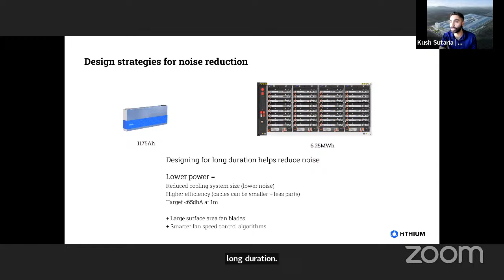We're trying to use larger flat fan blades, as well as smarter fan speed control algorithms which modulate the speed of the fan so it's not running at full power all the time, giving more granular control of fan speed. For this, we're targeting around 65 dBA at 1 meter. So despite having more energy because you're running it slower, that will reduce the noise. This may be something you see more of in the industry, batteries being designed specifically for long duration, which hopefully will help trend noise downwards on these containers.